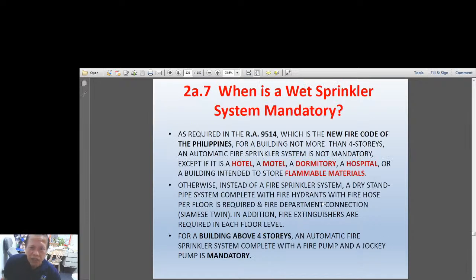But what is the basic requirement of the fire code today, the Philippine Fire Code? My interpretation is that if a building is used as a hotel, a motel, a dormitory, a hospital, then automatically you have to provide a sprinkler system. Automatically. Even if it is less than 15 meters. In the old fire code, it mentions 15 meters and above, that's the time you provide a sprinkler system. In the new fire code, the 9514 fire code, even if it is less than 15 meters, even if it is 1 story, 2 story, 3 story, 4 story, as long as it is used for hotel, motel, dormitory, and hospital, meaning to say guests are sleeping in the house or in the hotel, then you have to provide a sprinkler.